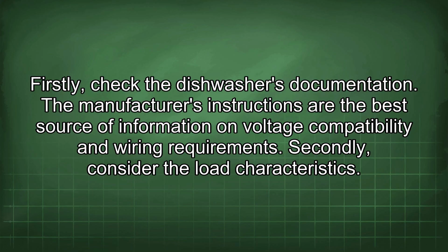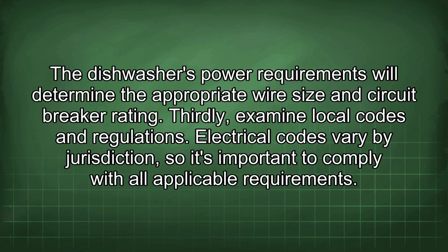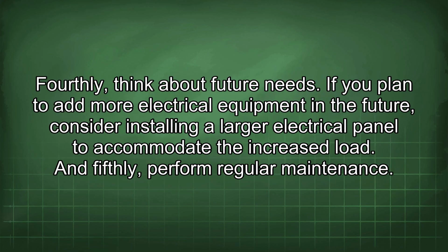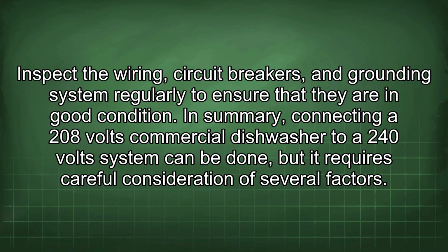Secondly, consider the load characteristics. The dishwasher's power requirements will determine the appropriate wire size and circuit breaker rating. Thirdly, examine local codes and regulations. Electrical codes vary by jurisdiction, so it's important to comply with all applicable requirements. Fourthly, think about future needs. If you plan to add more electrical equipment in the future, consider installing a larger electrical panel to accommodate the increased load. And fifthly, perform regular maintenance. Inspect the wiring, circuit breakers, and grounding system regularly to ensure that they are in good condition.